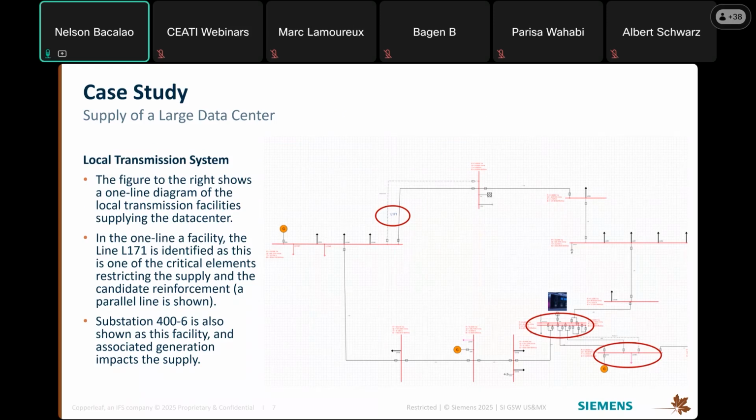And that's where this link that we're doing between our tool, which calculates the probability of failure, and Copperleaf is fundamental, because we're getting from Copperleaf Asset, which looks at the actual performance of the assets in the network, what we call the PRB files. The PRB files tell us the frequency of failure of this asset and how long it takes to be repaired. And more interestingly, it gives us over time, as the asset ages, the probability of failure increases.